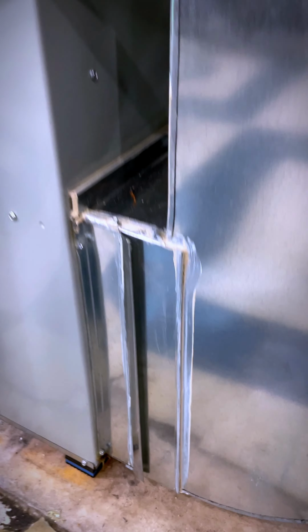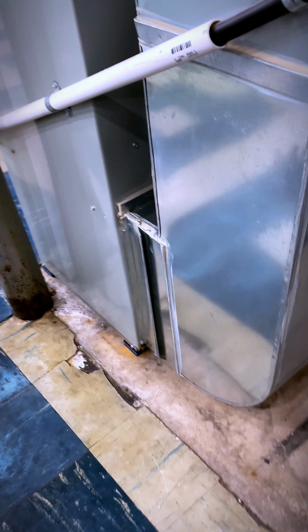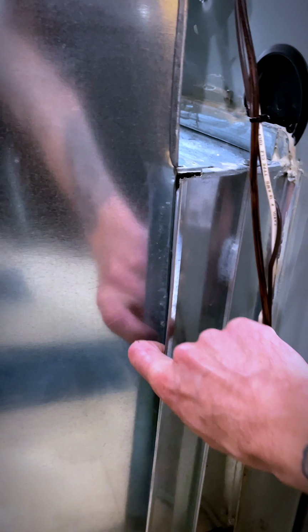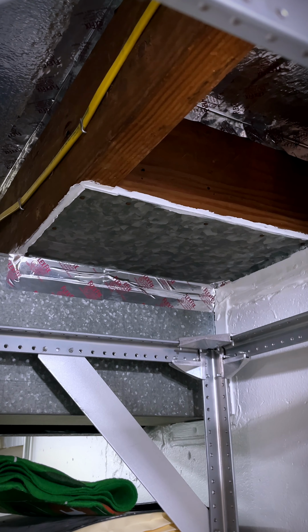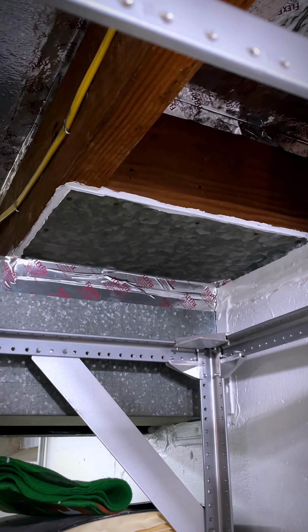All these systems come with a door on each side because you don't know which side of the system is going to end up against the wall, and you need to be able to access your filter, which on my system is done over here. I also went through with OSI Quad caulk between the wood and the sheet metal for all the return ducts, so there's no air leaks on the intake side.